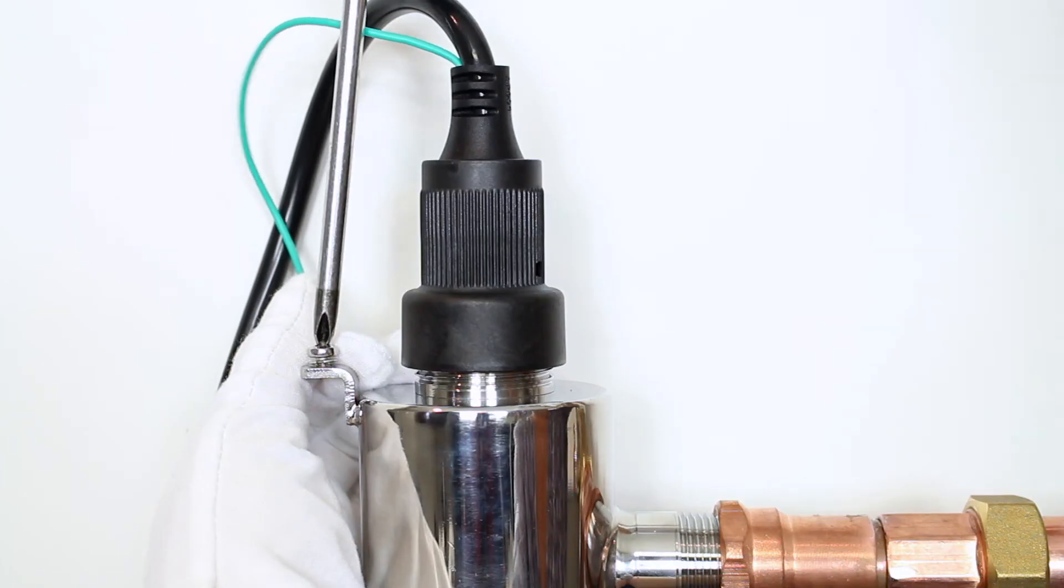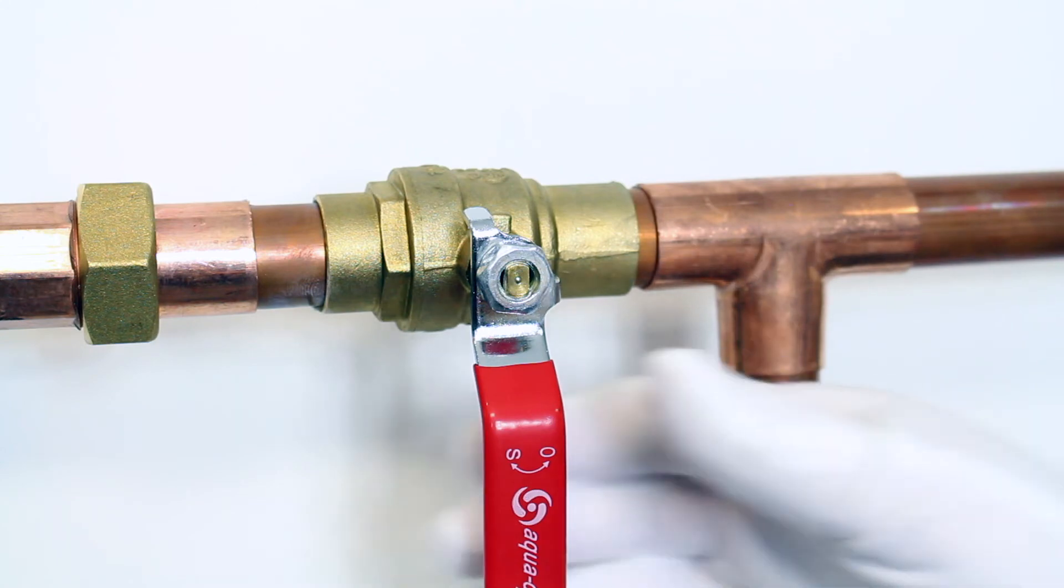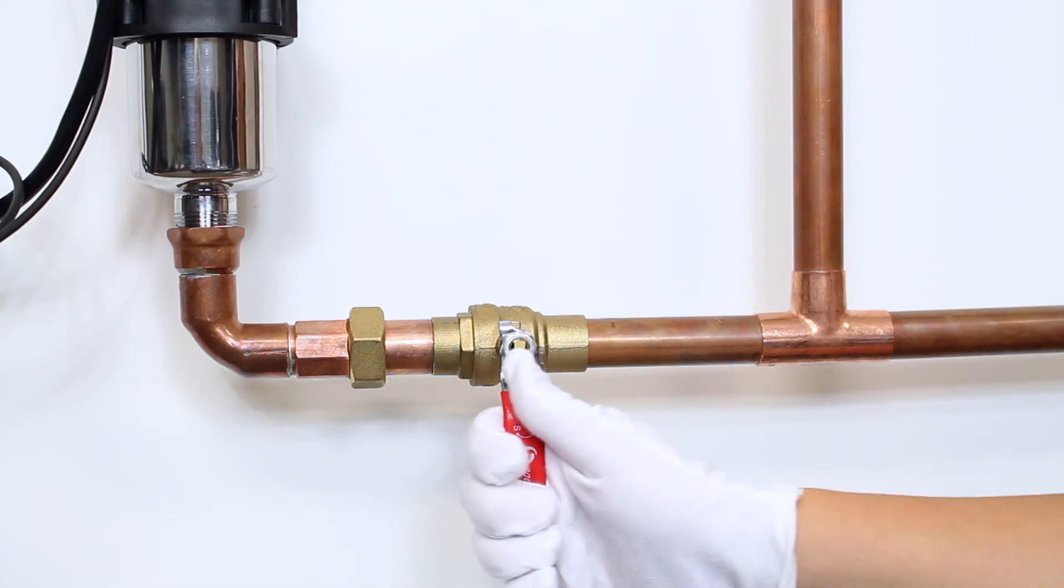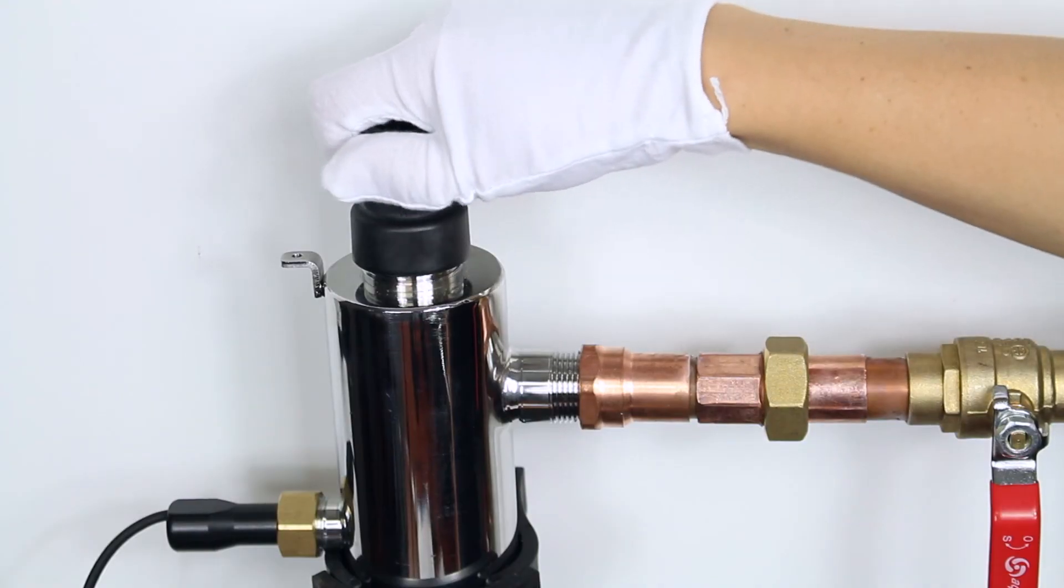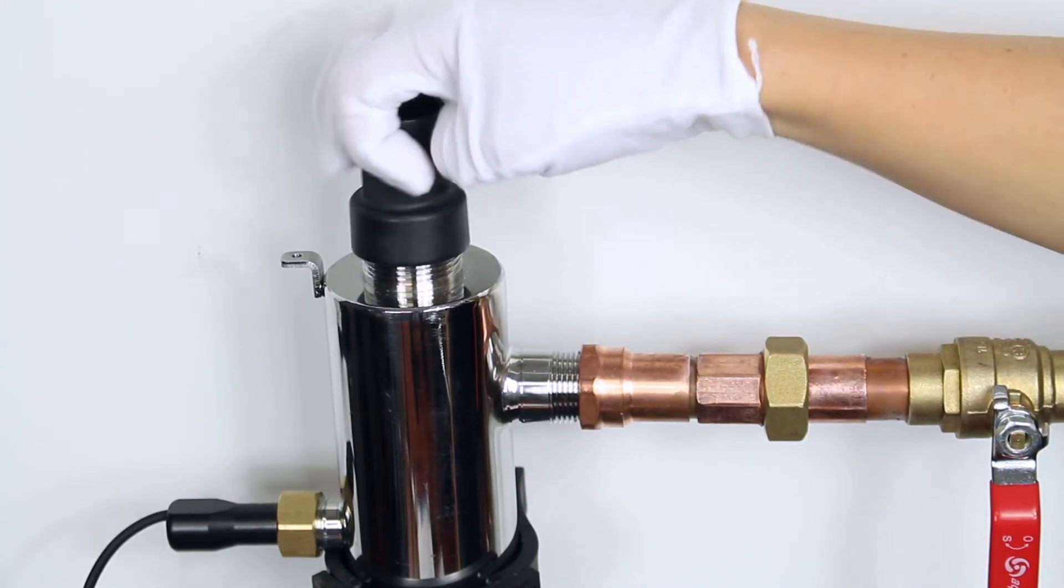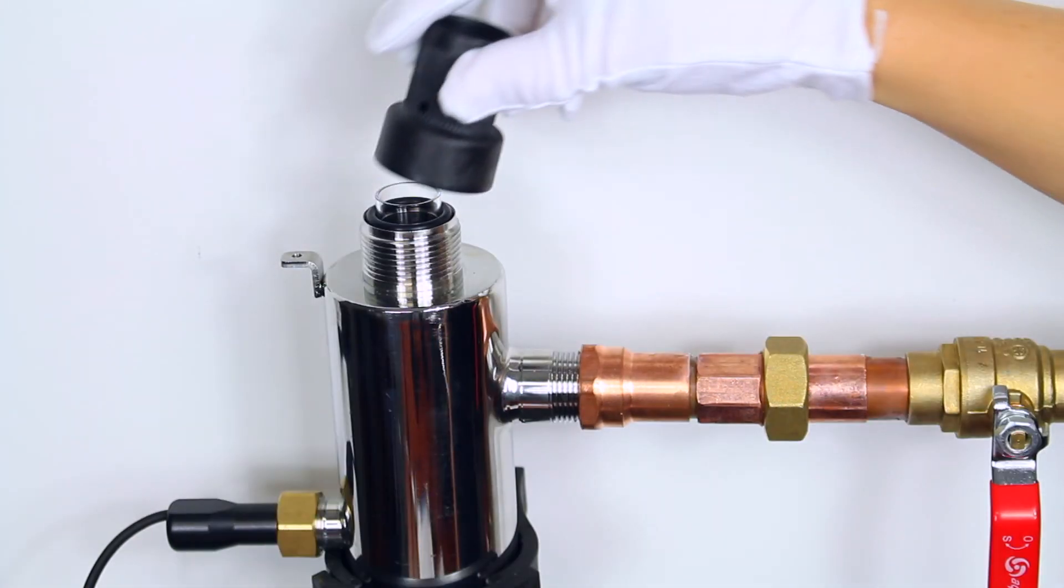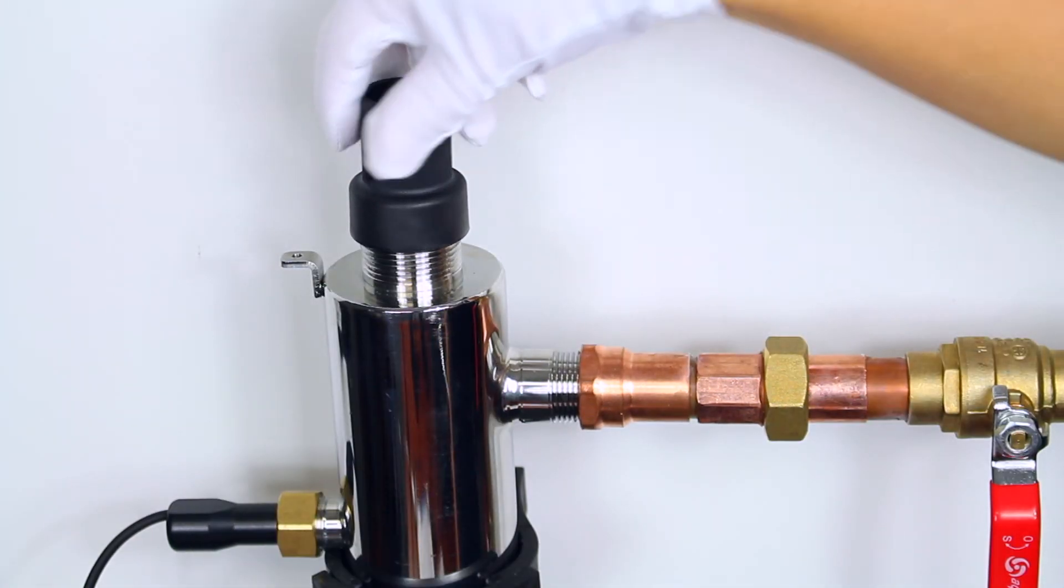Tighten the ground screw back on the ground lug on the UV reactor. Slowly turn the water back on to ensure that there is no leaking from the gland nut. If there is, turn the water off again and take off the gland nut. Make sure that the o-ring is fully seated up against the reactor and try again.